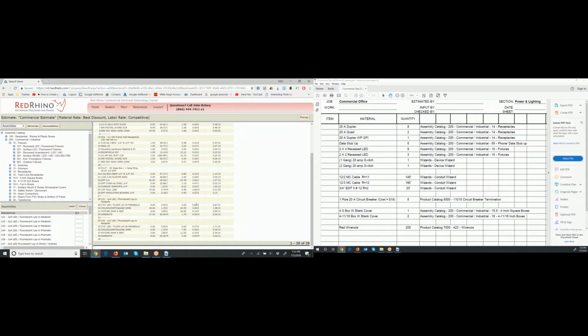The output also was 2 ceiling wires, sometimes called earthquake wires, for each fixture. Now, a lot of times when we're bidding public jobs, like for the state or county or city, they require one earthquake wire, one ceiling wire per fixture. If so, I would edit this number and just double it. I'm not going to do that here, but that's what I would do if I had to.